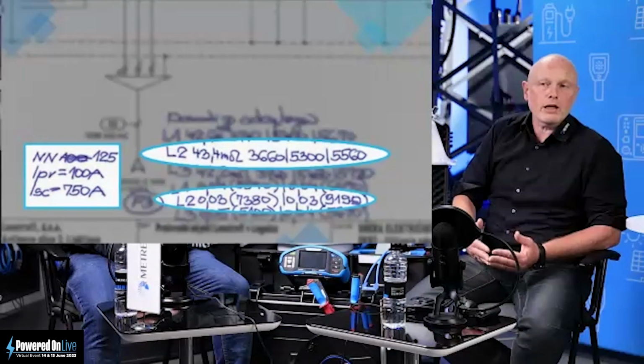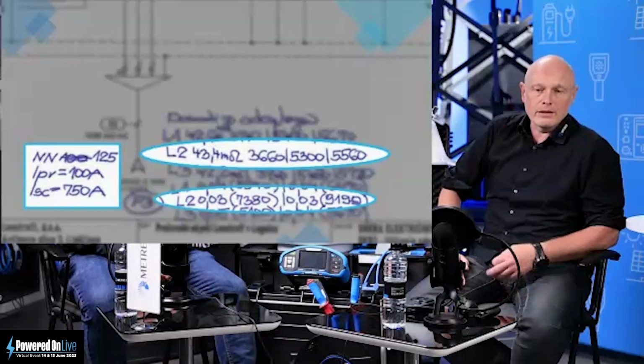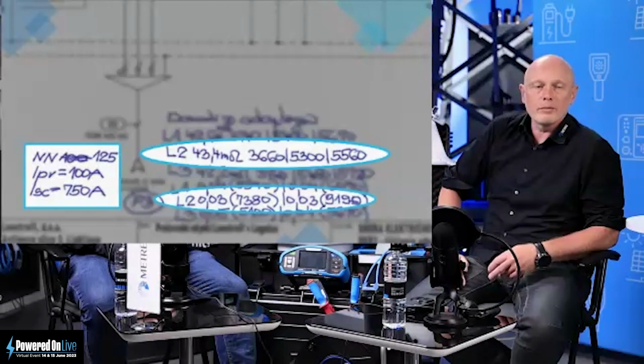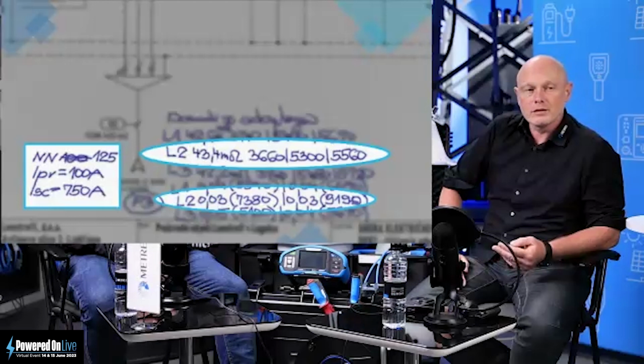The first thing to check when you go to the field is the rated nominal current of the fuses present in this sector. Whenever the fuses have nominal currents above 63 amps, the test and measurement equipment needs to be selected with special care.